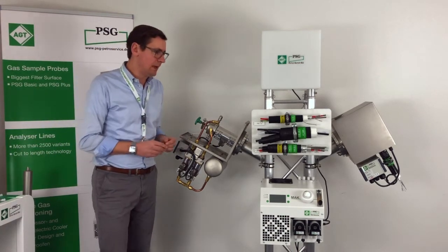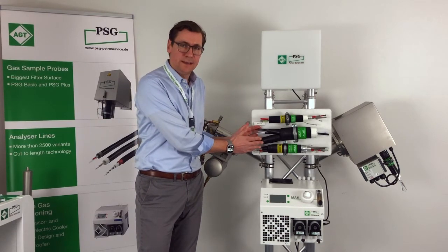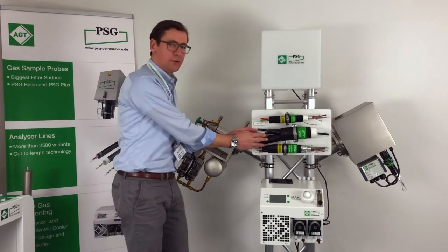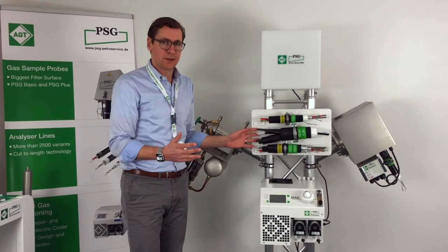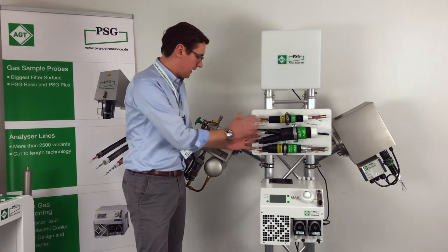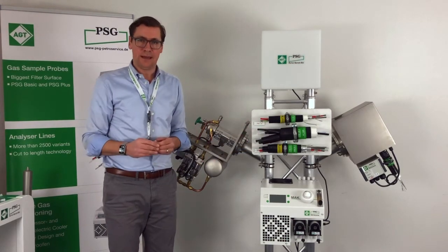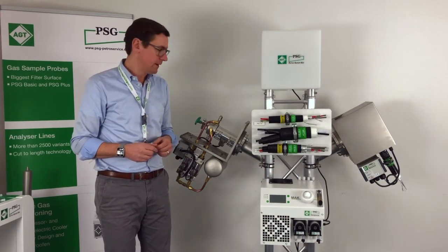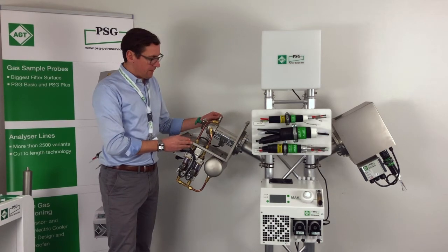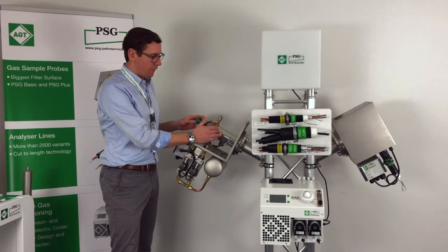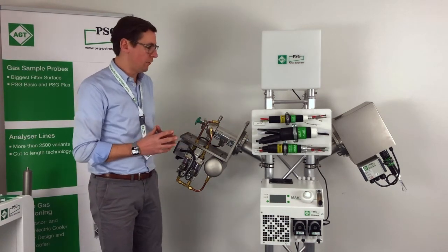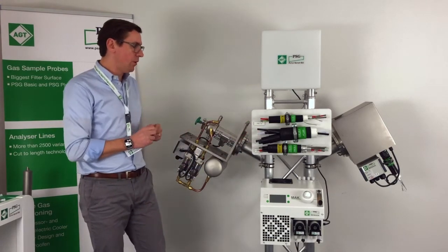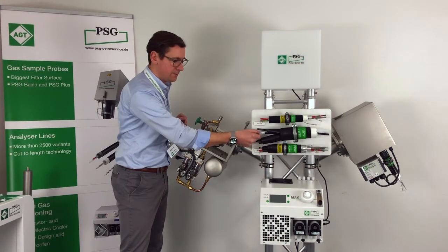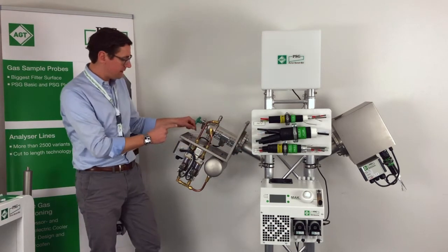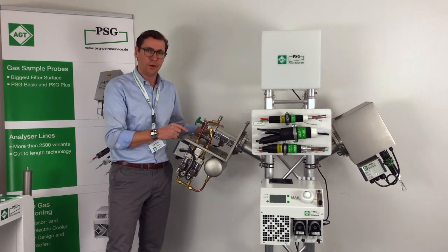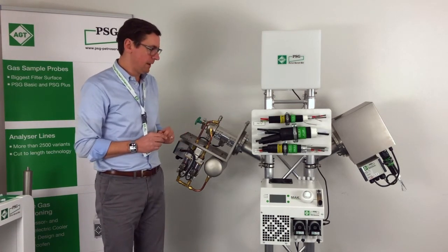The concept of the PSG Hybrid Line is that all infrastructure which is needed in order to operate the probe is integrated into the line. The big advantage is that you can operate the entire probe directly from your analyzer shelter. Let me explain to you how that works. If we have a look at the probe, we need a power supply for the heater, for the ring heater, which heats the probe. This is the cable you can find here. Furthermore, it is needed to control the temperature of the line. This is the PT100 cable you can find here, and this PT100 cable is directly connected to the probe. So you can control the temperature of the probe like this.